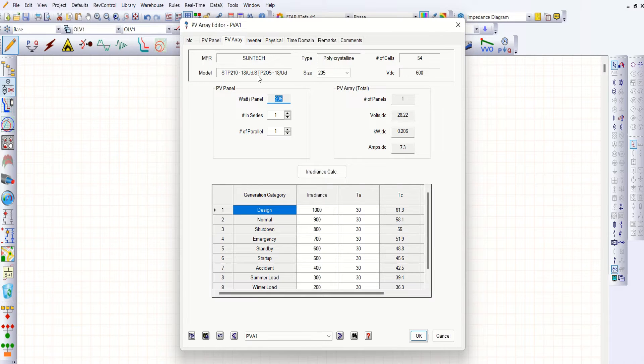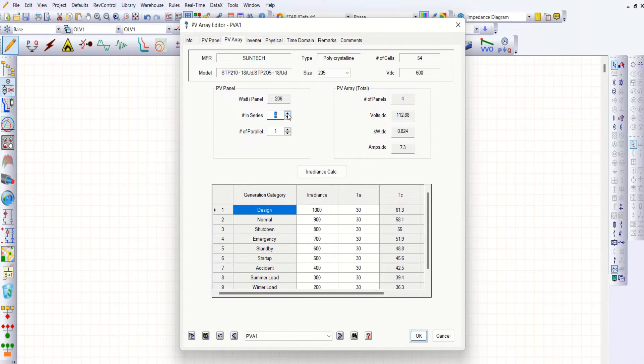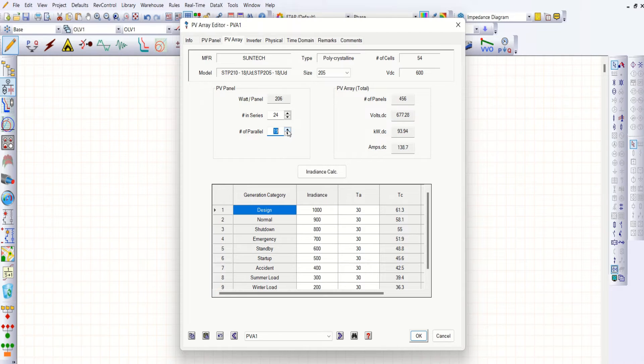Then go to PV array. I want to develop a series-parallel combination of these PV panels so that I can formulate a PV array. I'm going for about 200 kilowatt power. Increasing series-connected panels increases your voltage as well as power. Let me increase this to 24, so that I approximately get a DC voltage of 677V. You can also increase parallel — amps and power increase. Let me increase this to about 48, so that I may get approximately 237.3 kilowatts and 350 amps.